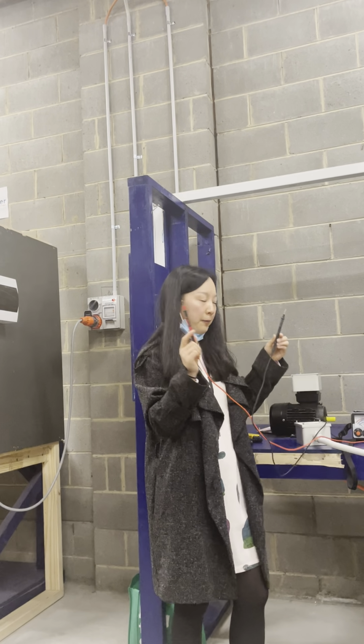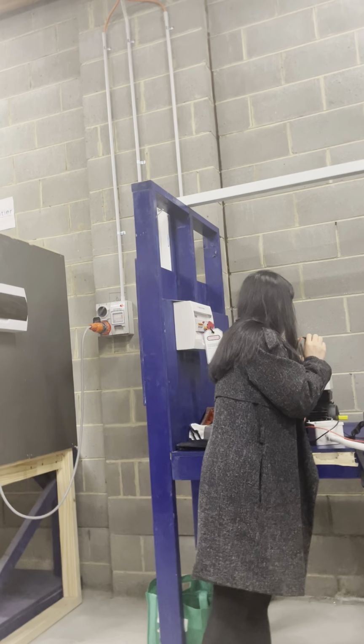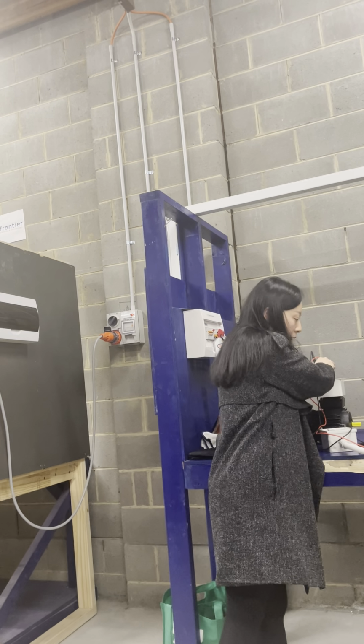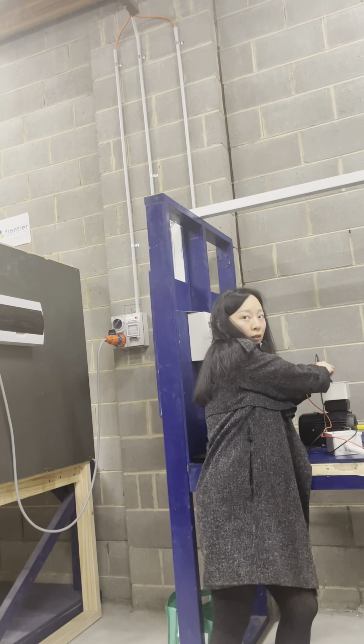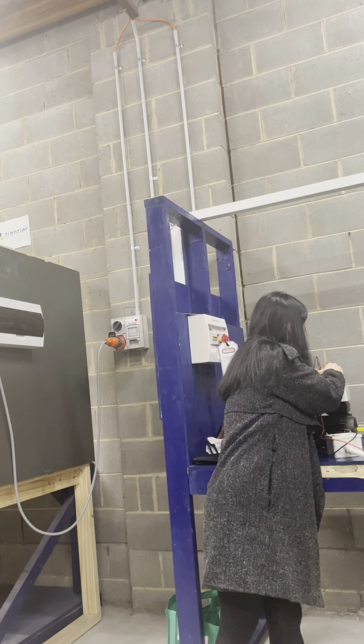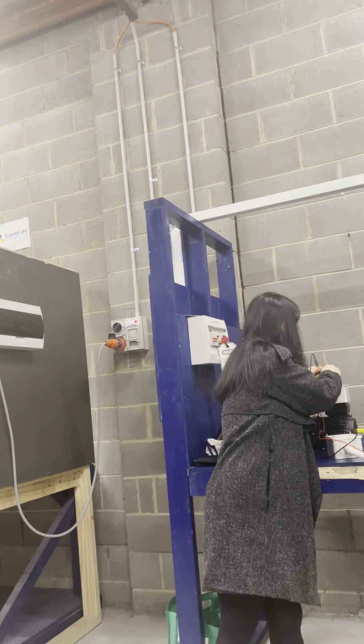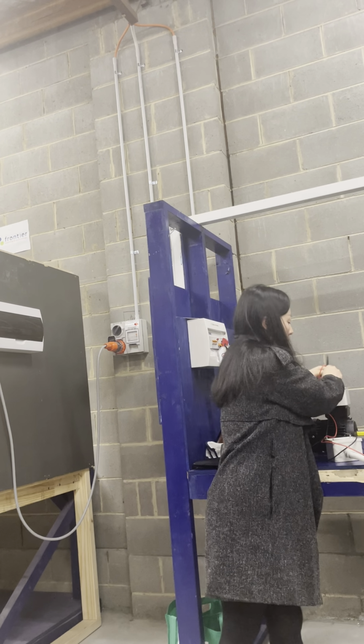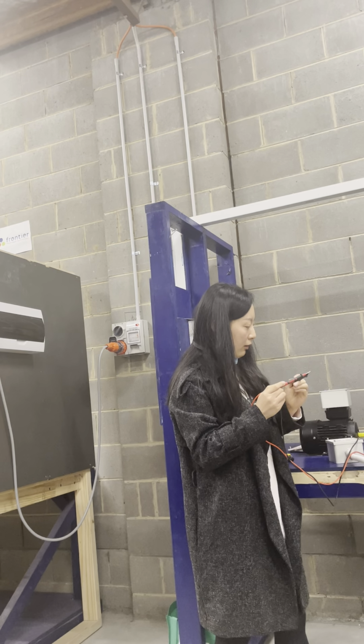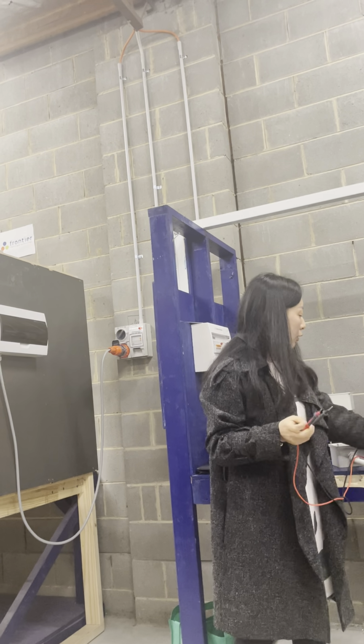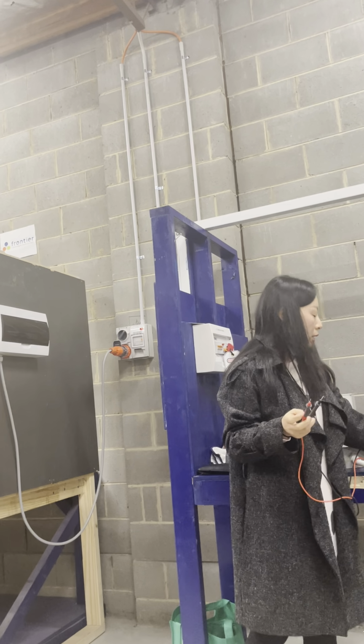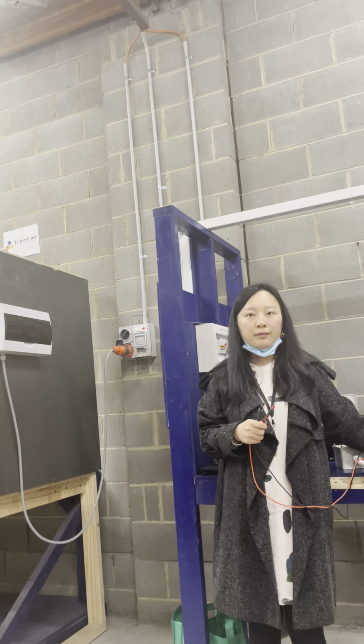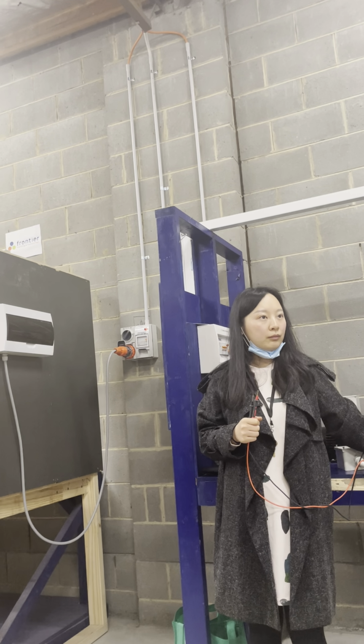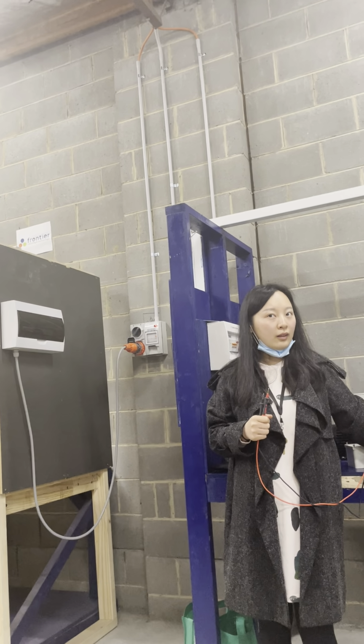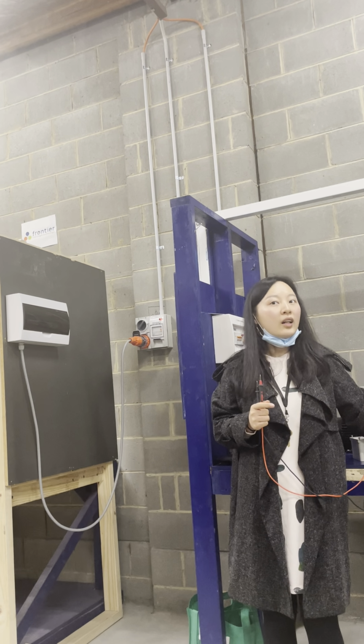Okay, I'm checking between earth and phase 1. What's the value? Infinity. Yeah, that's good. Phase 2? Same. Phase 3? Same. Now we test your tester. That's good. What's the pass value? What's the minimum requirement for the IR test? Less than 1 mega ohm. Oh, sorry. More than 1 mega ohm. Correct.